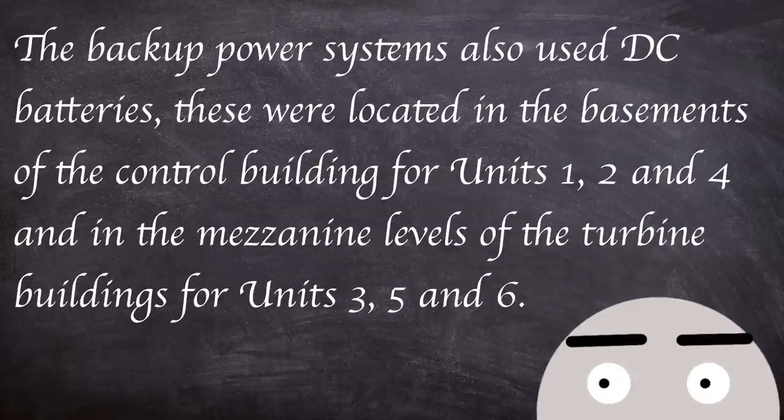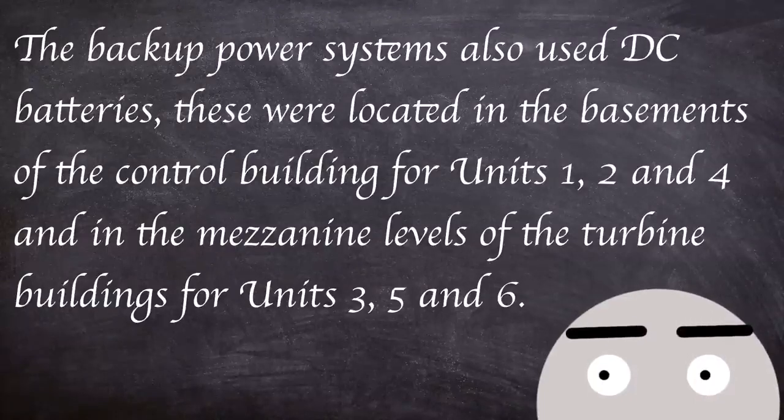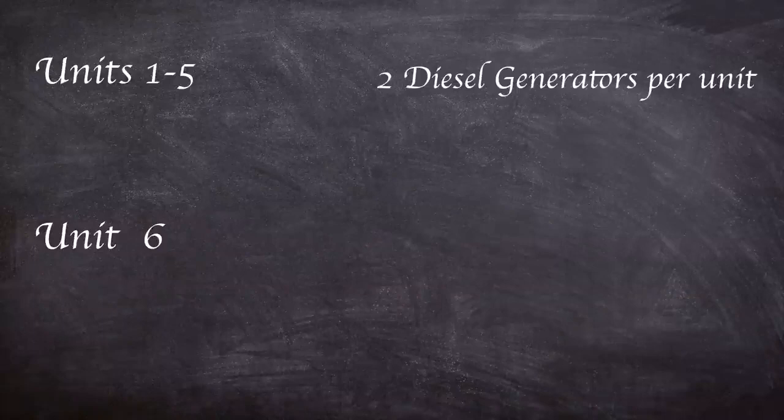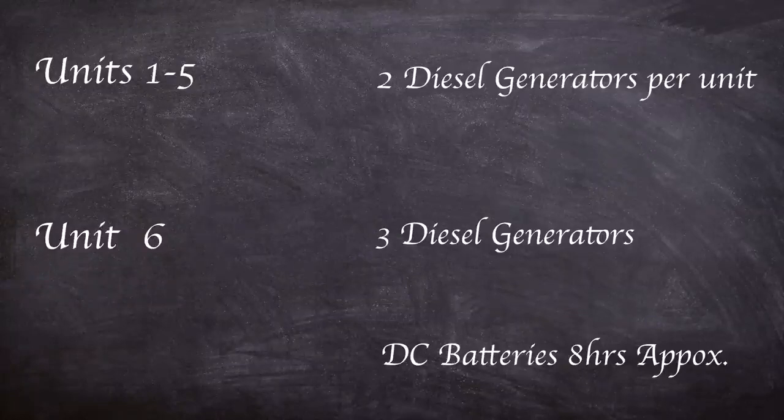The backup power systems also used DC batteries located in basements of control buildings for units 1, 2, and 4, and in mezzanine levels of turbine buildings for units 3, 5, and 6. Units 1 to 5 had two diesel generators each; unit 6 had three. The batteries gave up to eight hours of emergency power in case of grid isolation.